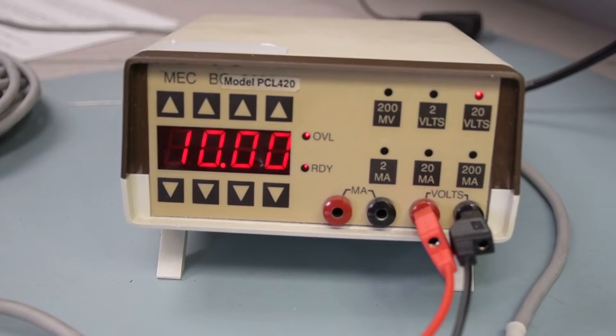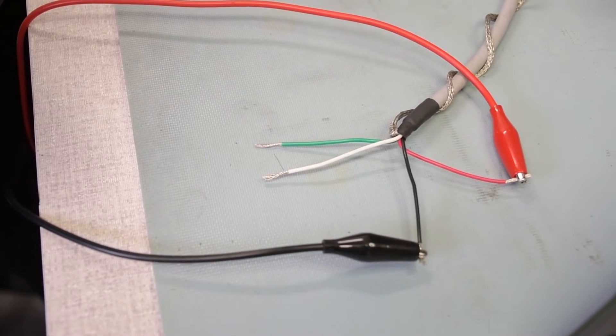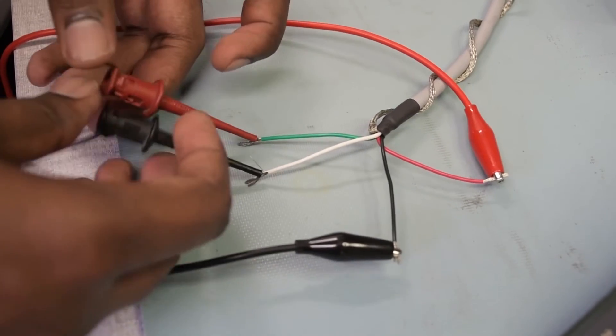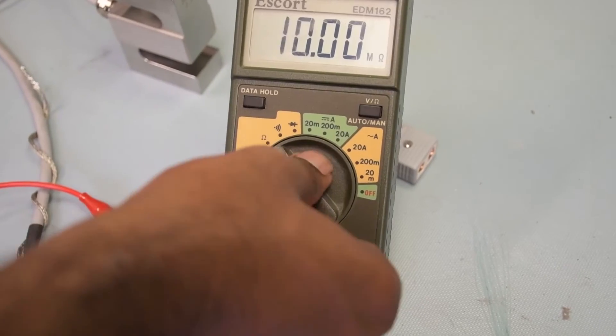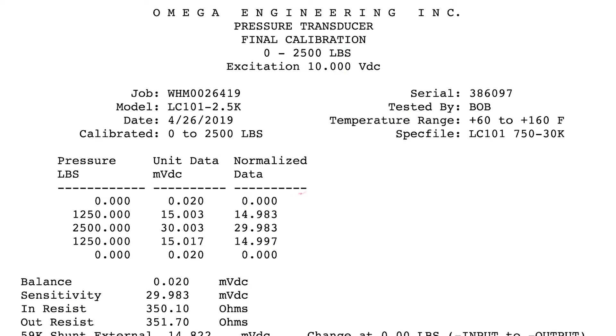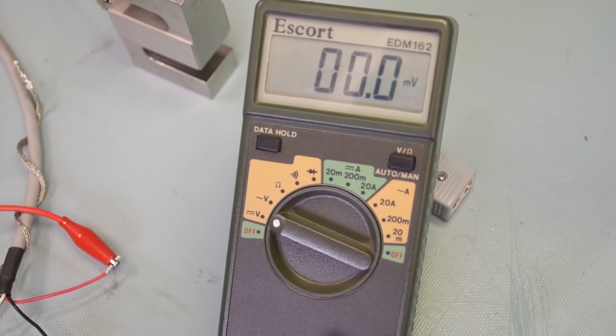Since that is good, I'm going to apply 10 volts DC across my input leads, and now I'm going to measure the millivolts signal across my green and white wires, which are the signal wires. If you look in the calibration certificate, at no force being applied, you should read close to zero millivolts. I'm reading 0.0.